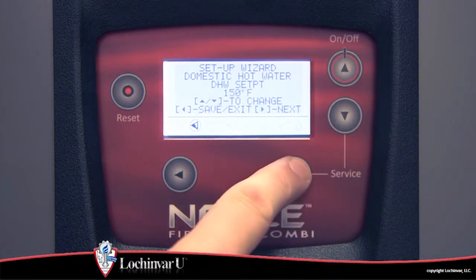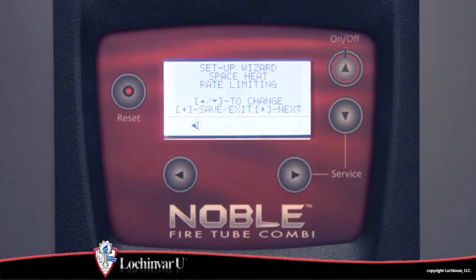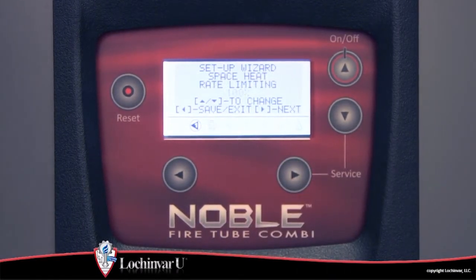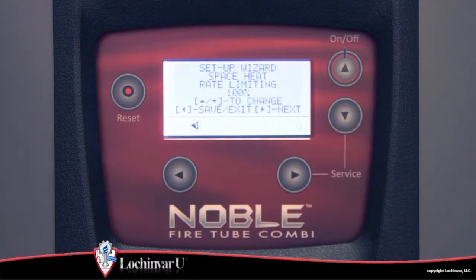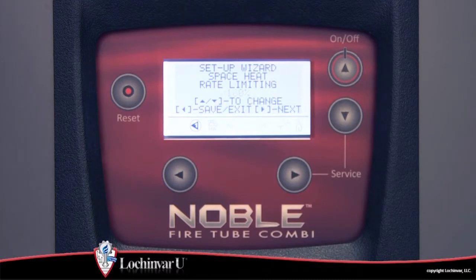The ninth parameter visible is space heat rate limiting. When the maximum space heating load is less than the maximum input of the unit, this setting will limit the firing rate of the unit during a space heating demand only.